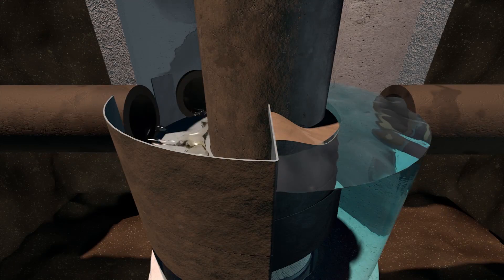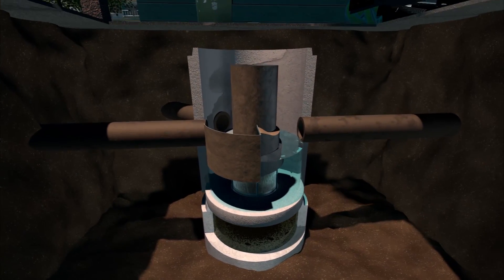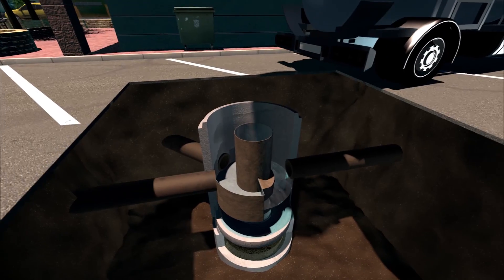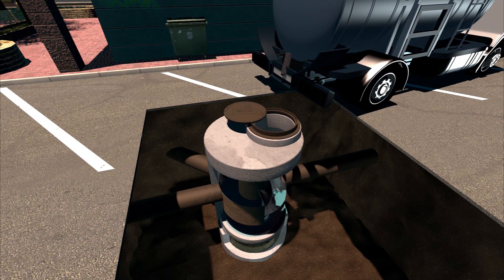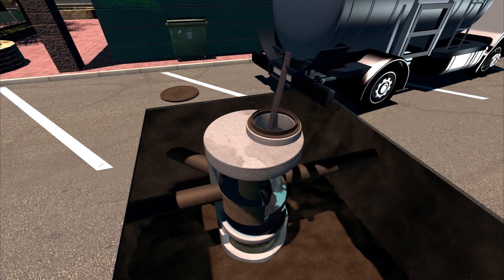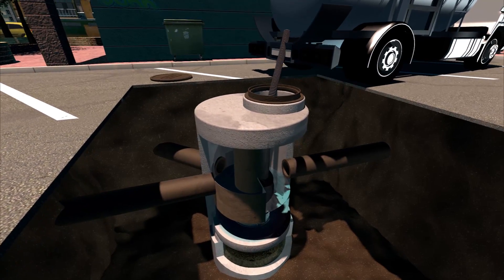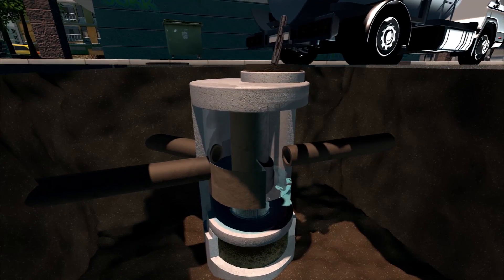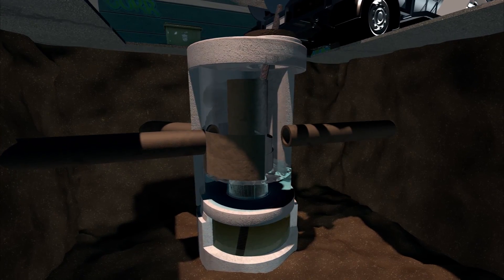When the storm event ends, the water surface is returned to the outlet pipe elevation. The CDS system should be inspected at regular intervals and maintained when necessary to ensure optimum performance. Maintaining a CDS is a simple process that can be easily accomplished in less than 30 minutes for most installations using a vacuum truck, with no requirement to enter the unit.